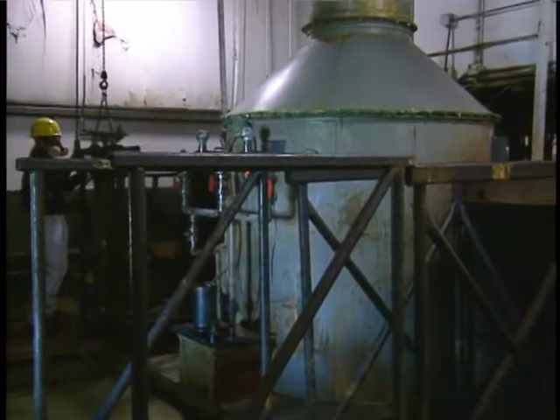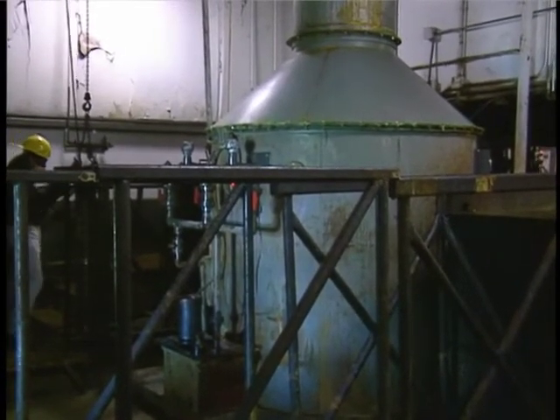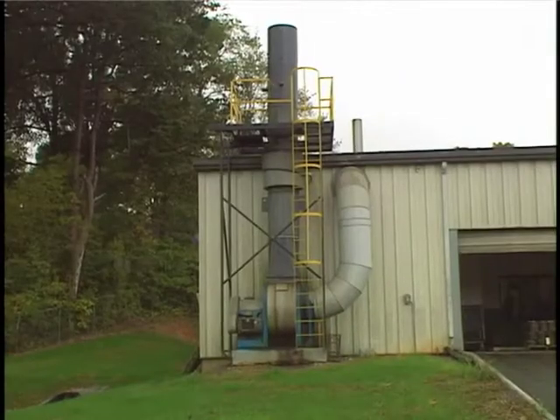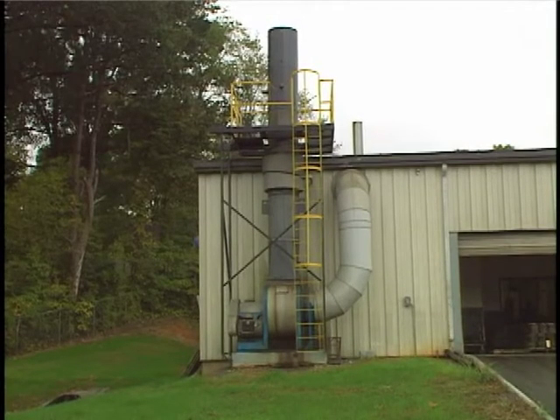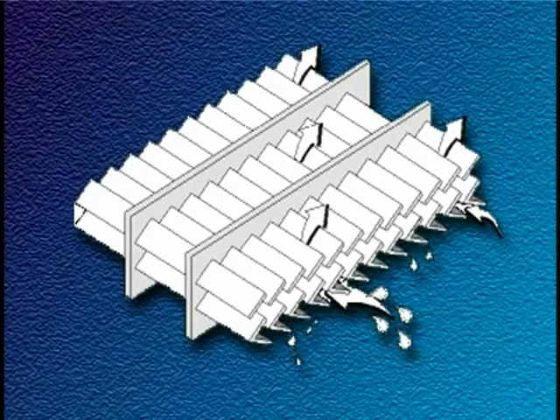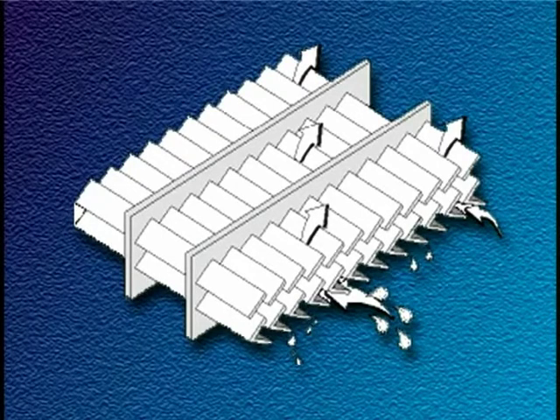In all wet scrubbers, the process of contacting the gas and liquid streams results in entrained droplets. Since these droplets contain the contaminants, they must be removed before the gas stream exits the unit. This is referred to as mist elimination or entrainment separation. The most common mist eliminators are chevrons, mesh pads and cyclones. Chevrons are simply zig-zag baffles that cause the gas stream to turn several times as it passes through the mist eliminator. The liquid droplets are collected on the blades of the chevron and drained back into the scrubber.